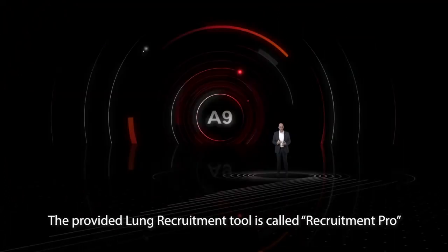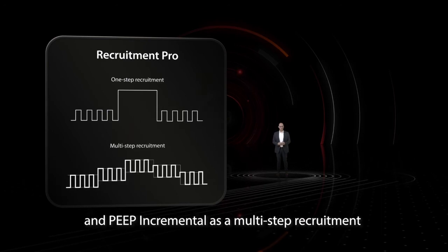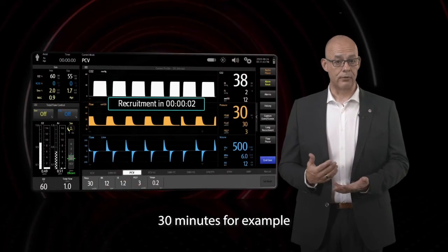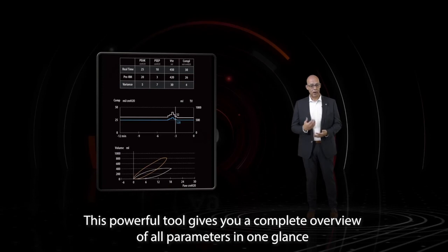The provided lung recruitment tool is called Recruitment Pro. It offers sustained inflation as a one-step recruitment and PEEP Incremental as a multi-step recruitment. We can even schedule the recruitment intervals automatically — 30 minutes for example — to make the recruitment more efficient during long-term surgery. This powerful tool gives you a complete overview of all parameters in one glance.